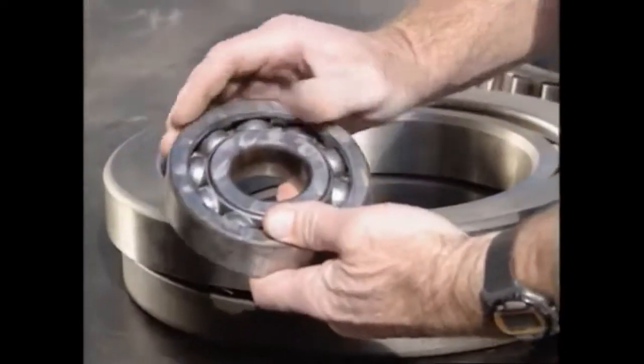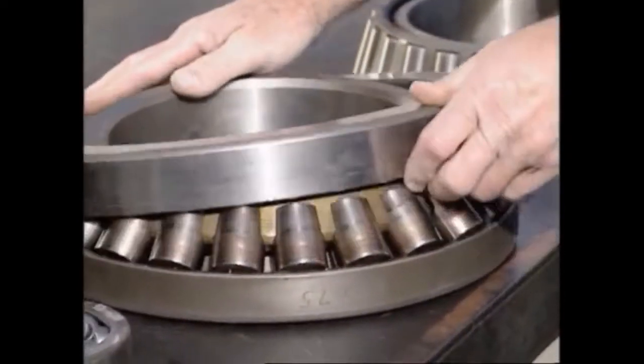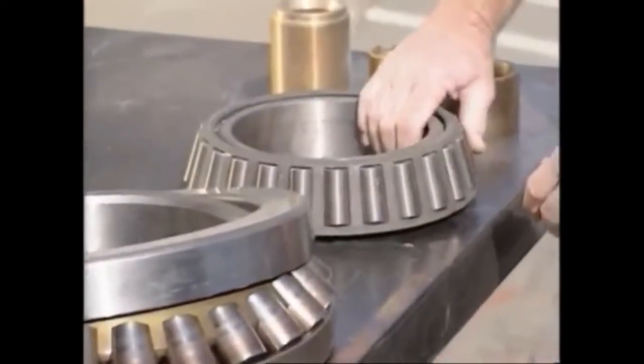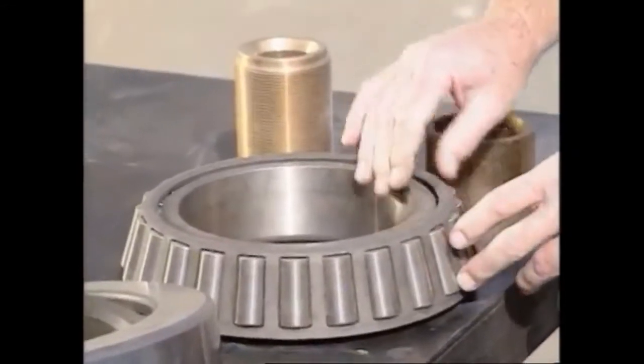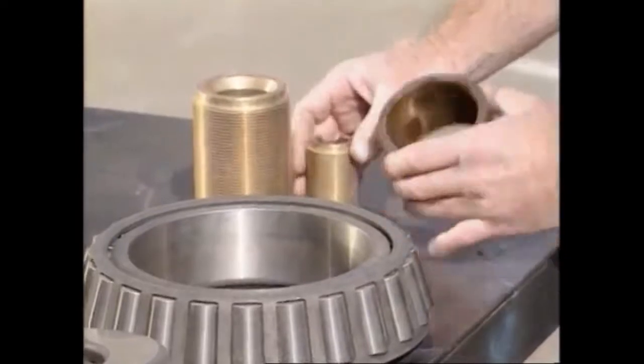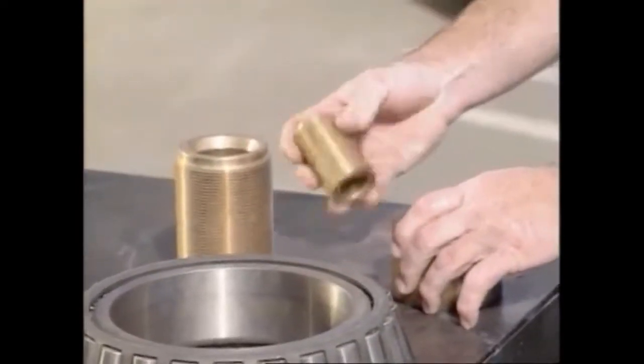Pump bearings should usually last for years if serviced properly and used in their proper application. Several types of bearings are used in pumps, such as ball bearings, roller bearings, and sleeve bearings. Each bearing has a special purpose, such as thrust load, radial load, and speed. The type of bearing used in each pump depends on the manufacturer's design and application. Whenever a bearing failure occurs, the bearing should be examined to determine the cause and, if possible, to eliminate the problem. Bearing failures are caused by fatigue failure, contamination, brinelling, false brinelling, thrust failures, misalignment, electric arcing, lubrication failure, and cage failure.